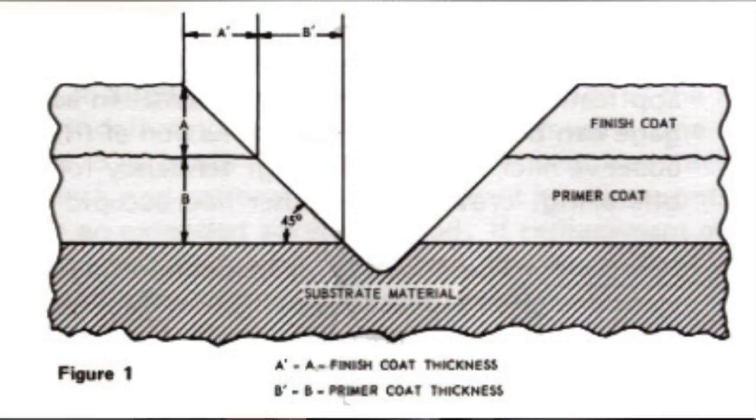The Tooke Gauge measures coating thickness using basic trigonometry. That is, by cutting a precision V groove into the coating system using one of the tips, a right triangle is created.